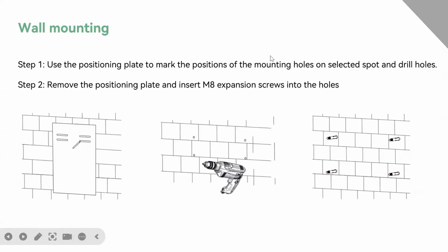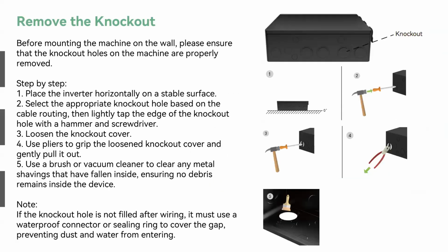And you may notice that there is some knockout on the side of the inverter, on the bottom of the inverters. So before we connect the wires, we have to remove the knockouts. You can either remove it when you take it out from the box, or you can remove it after you install it on the wall. You can follow the steps here to remove the knockout, and make sure to seal it after the cable connection to make sure that no dust, water, or bugs enter through the holes.